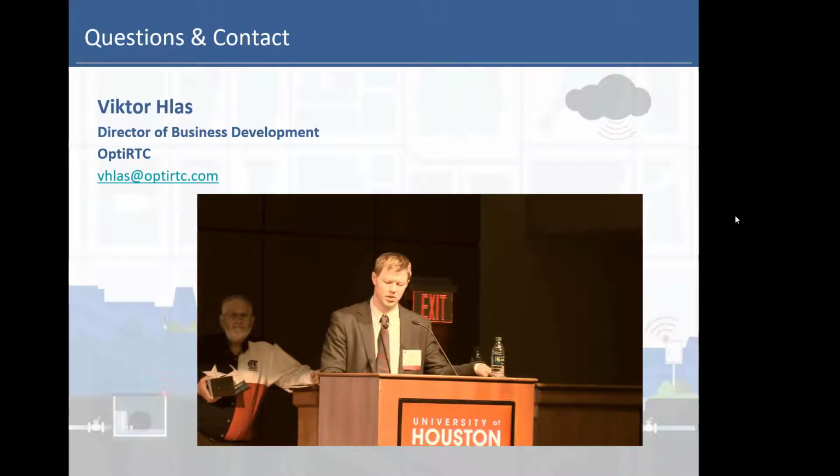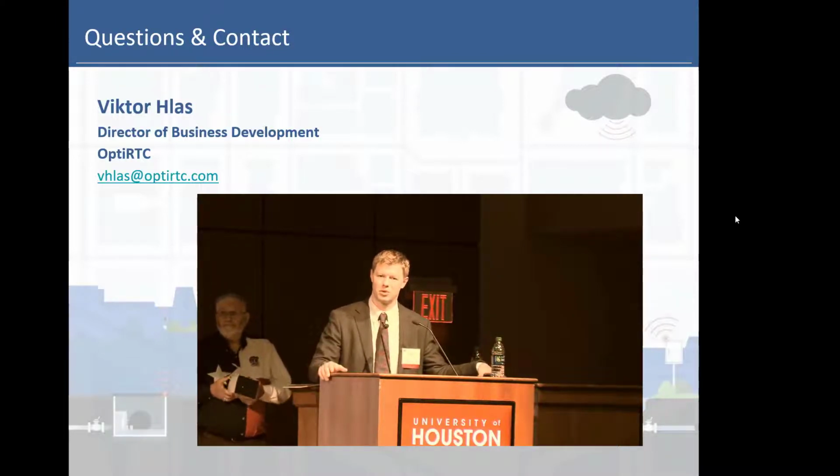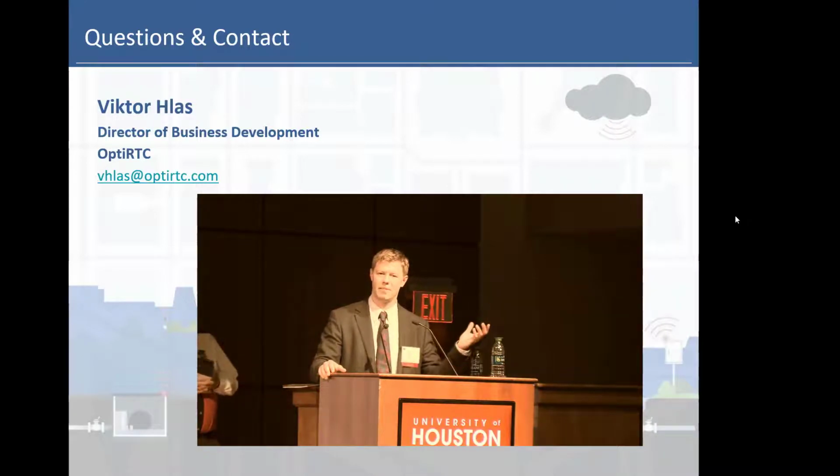And what goes into figuring out how much is two factors. One is looking at the NOAA National Weather Service and looking at the quantity of precipitation that's expected to run off the watershed area in the next 24 or 48 hours. And then looking at what storage capacity is available at the site. And it's really just a mass balance where we're looking at what's expected to come in and what capacity we have available.